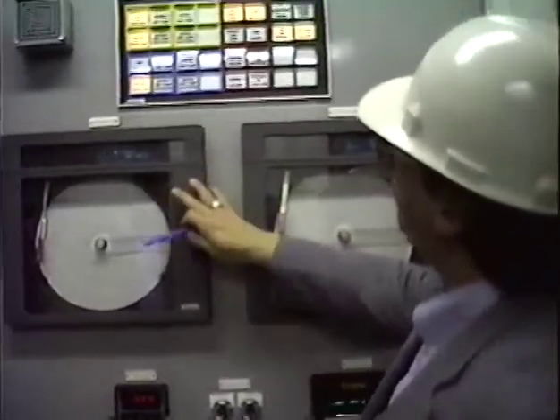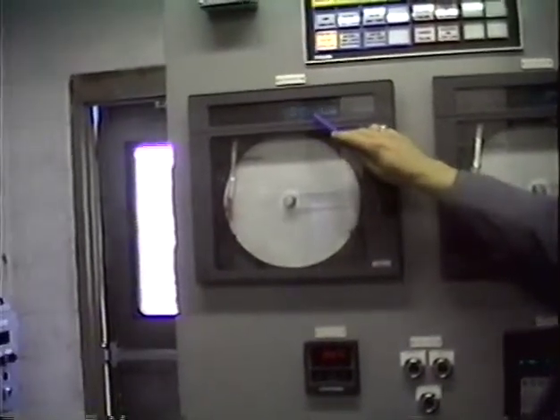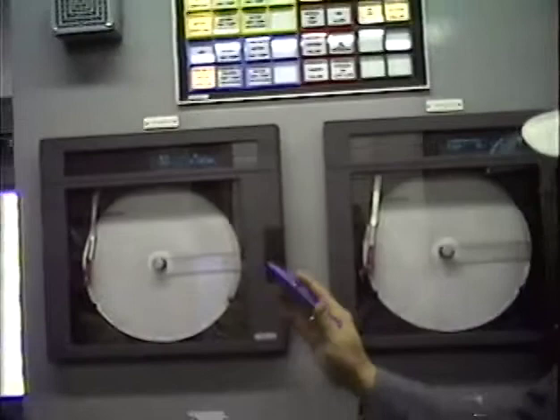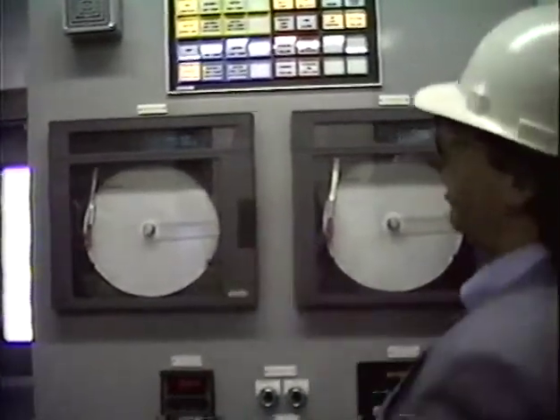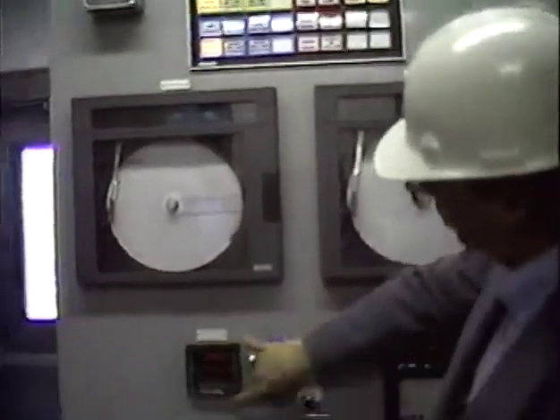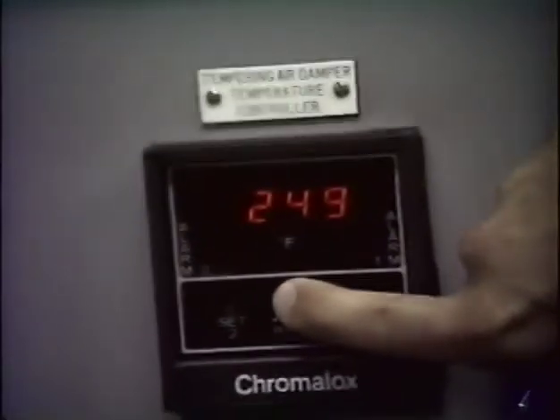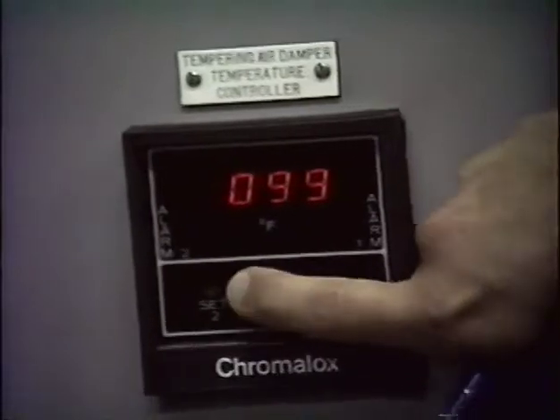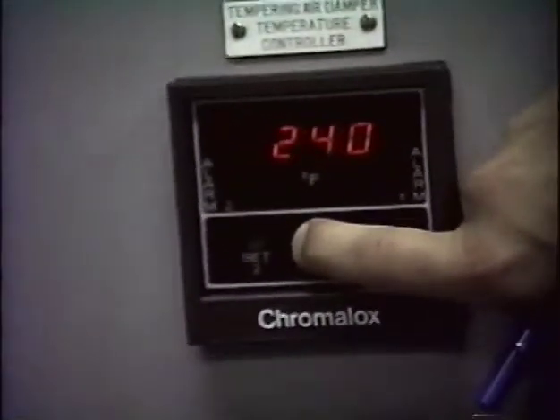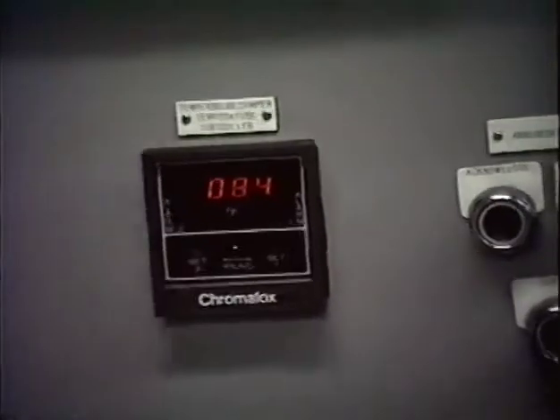This chart recorder, as we talked about, is for Baghouse inlet temperature and Baghouse delta P. The alarms off of this recorder go into this annunciator, as well as the alarm or set point of 6 inches to initiate a cleaning cycle of the baghouse. This little device here is for the tempering air damper control. The thermocouple is telling us 84 degrees in the duct. At 249 degrees, the tempering air damper would go open. At 240, it would go back closed. It's easily adjustable.